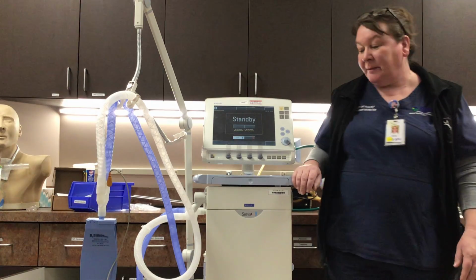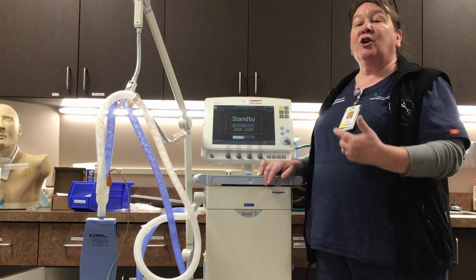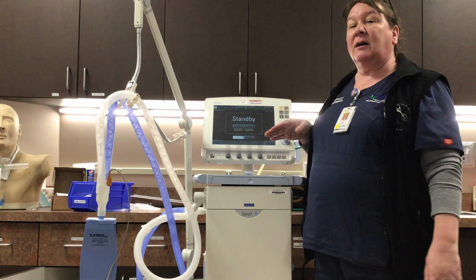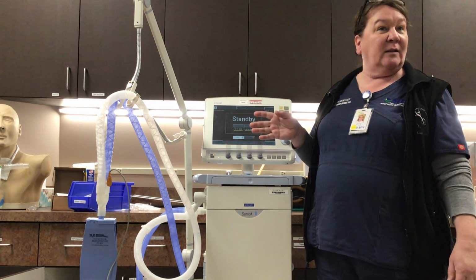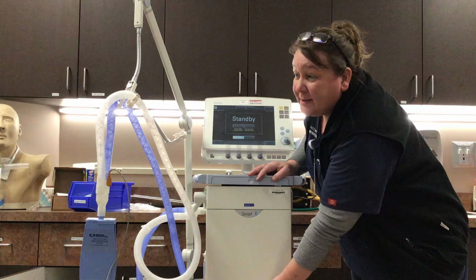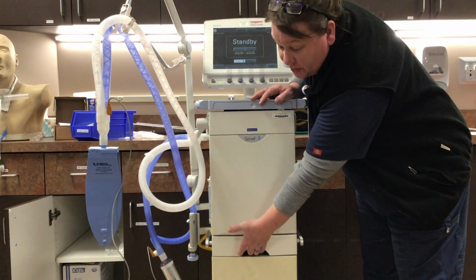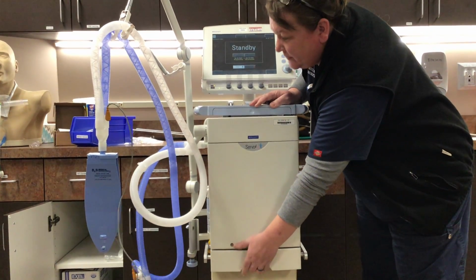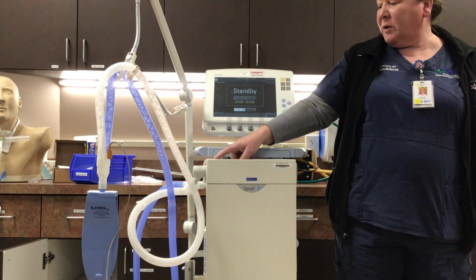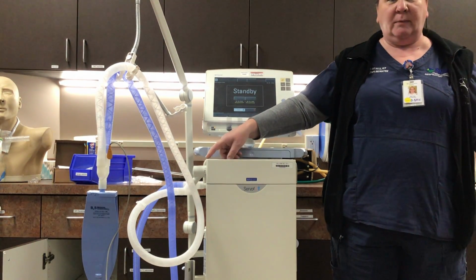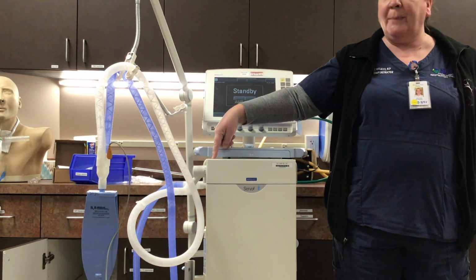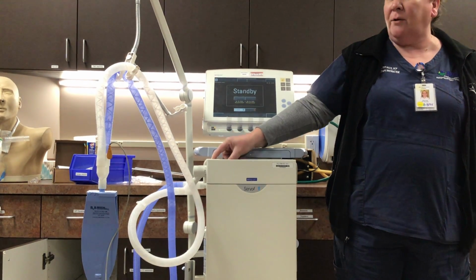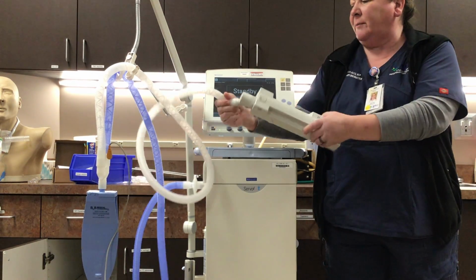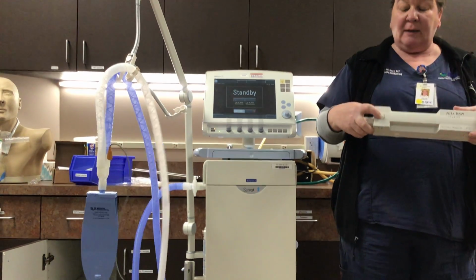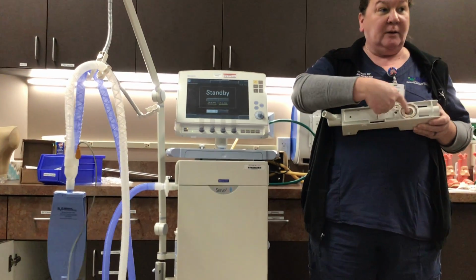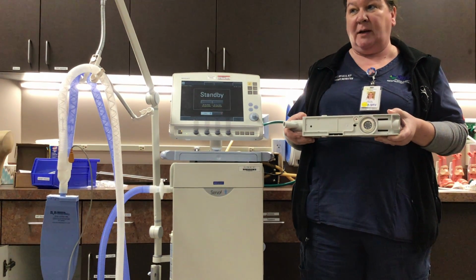Everybody ready? Okay. So the servo is actually, they call it an expiratory cassette, and you'll sometimes see it say check the expiratory cassette during the calibration. So on the servo, to get to the exhalation valve, you have to push this, there's a button right here. So this pushes up and then this pulls out. And then the expiratory cassette is right in here. Okay. And so there's a button that you push right here. You're gonna push that down and then lift it out. And of course I unhook it now. So this is the button I pushed, and then the expiratory valve is right here. So it's just that this one calls it an expiratory cassette instead.